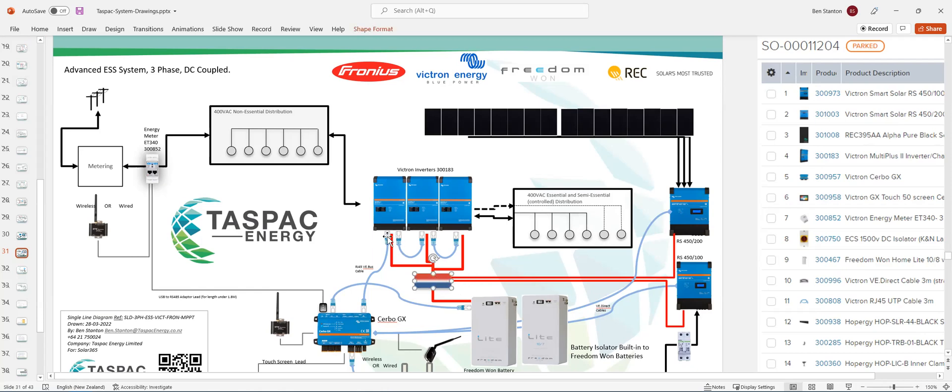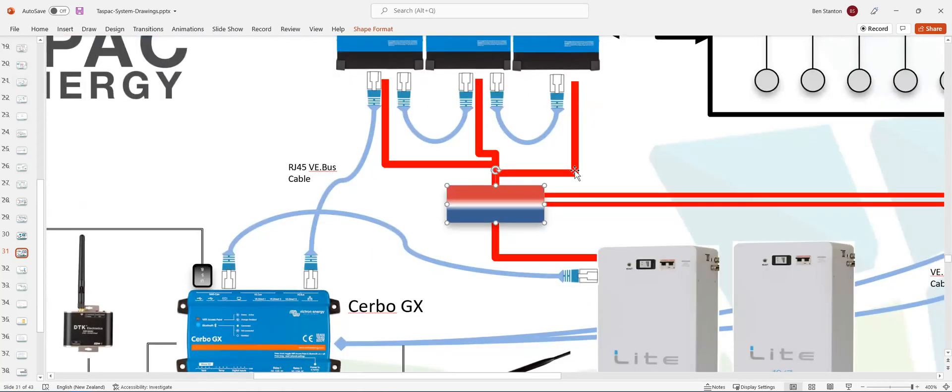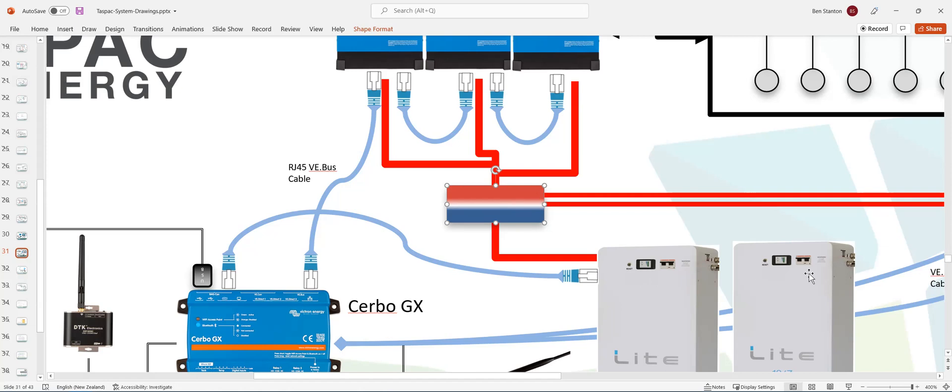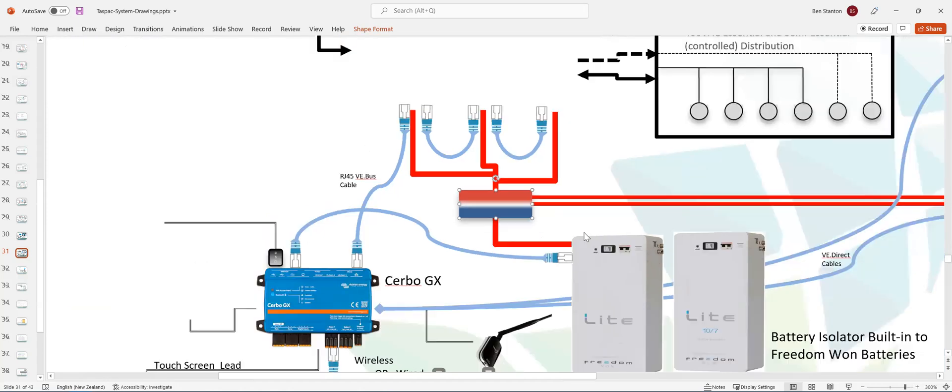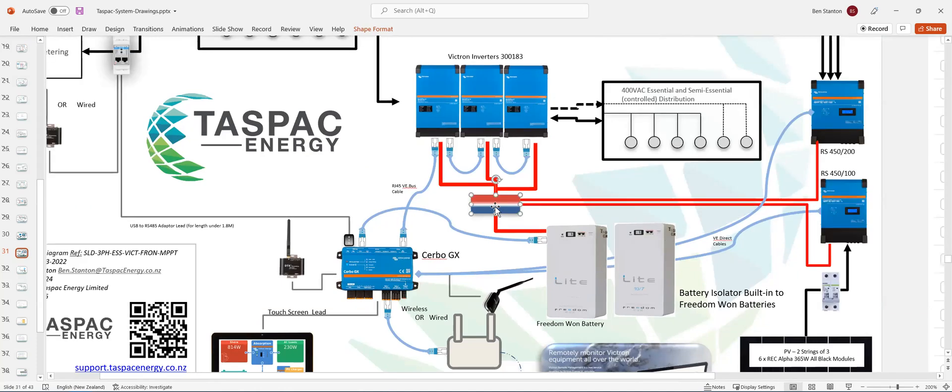But the DC side will all come back from the inverters. I've just done red cables there, but they're red and black, positive and negative. They will come back to a common point. Now, the batteries already have three meters of cable built in, positive and negative, 50 mil. You just need to take those to a common point, which could be a bus bar or simply a stud, and then bring positive and negative to each inverter.